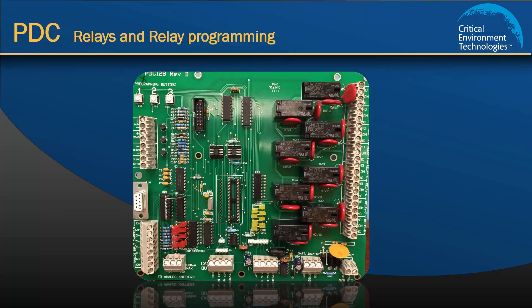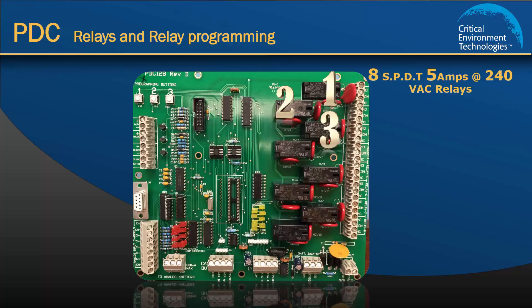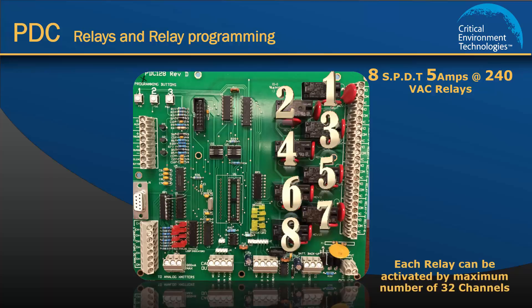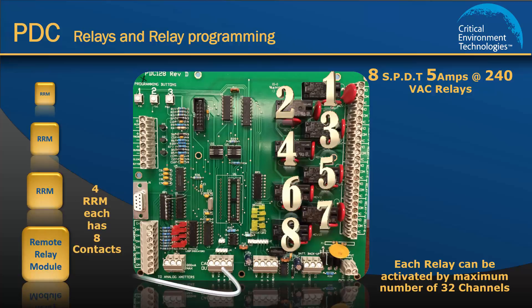If we take a closer look at the PDC from the inside, we notice that there are 8 failsafe relays. Each relay can be configured to monitor up to 32 channels for any alarm condition. In addition, up to 4 external remote relay modules can be added, each with their own 8 relays that can be configured and connected to the network. In this tutorial we will not be covering how to configure the remote relay modules — we are only looking at the relays inside the PDC.